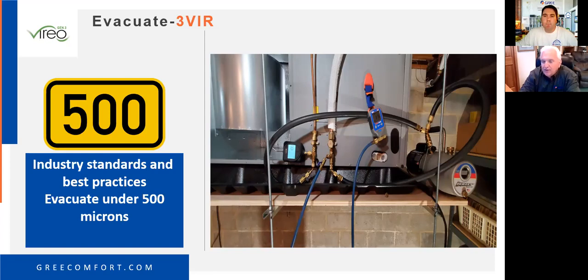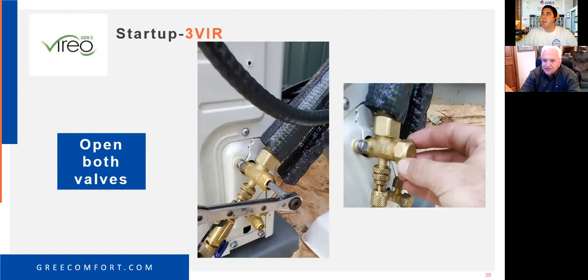And so as we're talking about new product today, these are all just repeats. So there's no real change in installation with the new Vireo Gen 3. These are just repeats of practices that we consider good practice for mini splits, correct? Most certainly. And I like to use that term, industry standards and best practices. That's what you're using for this system. There's nothing in particular that I found other than functions and features that changed. So as far as the install goes, you're following all your standard procedures. One of the big things that tends to come up is open both valves.